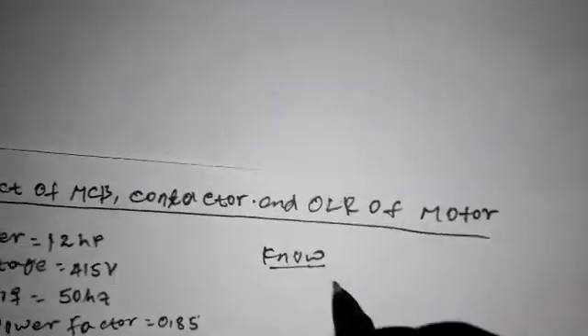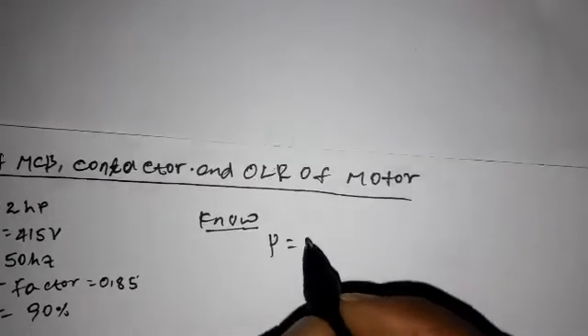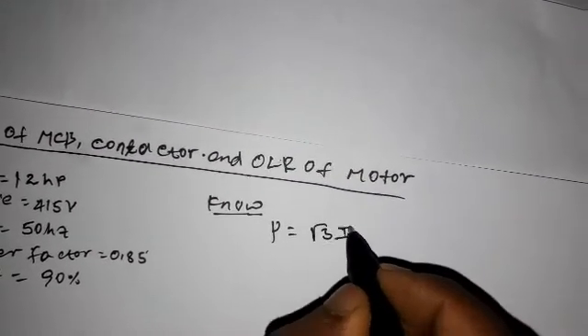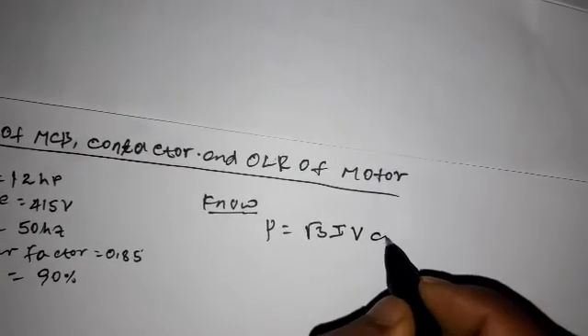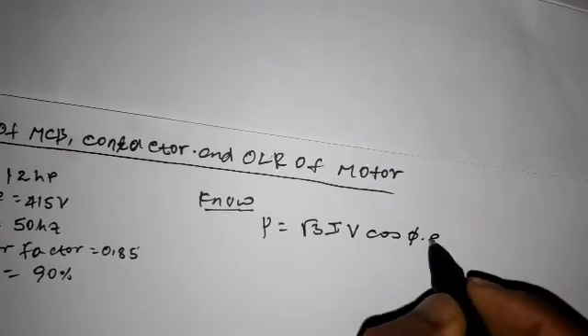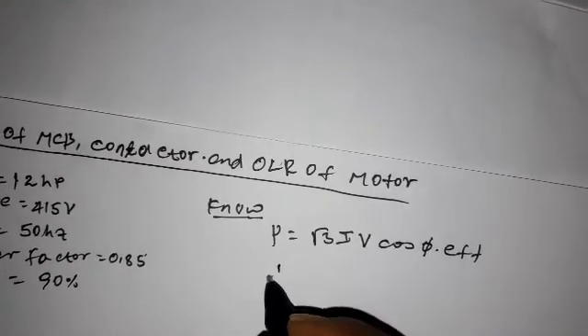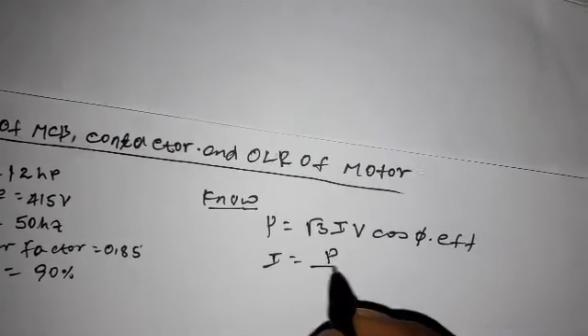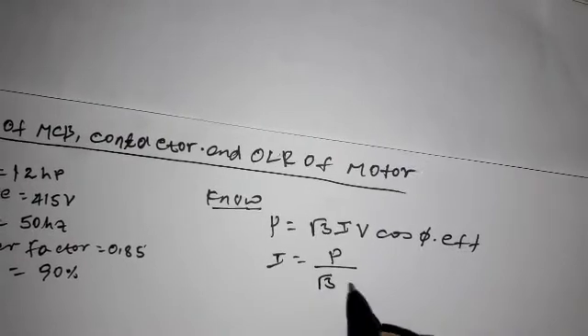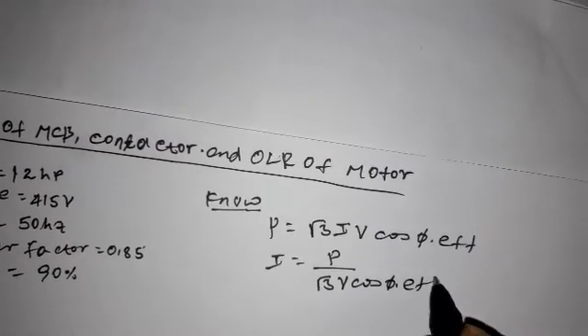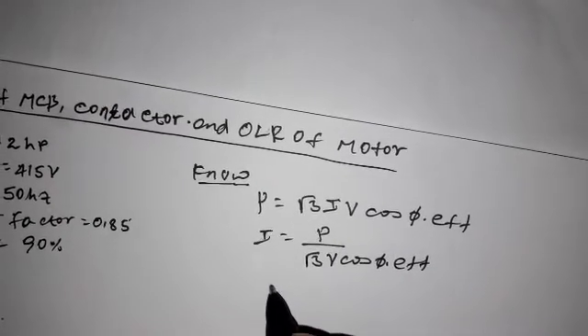Now, power is equal to √3 times current times voltage times cosine theta times efficiency. Then, current is equal to power divided by √3 voltage times cosine theta times efficiency.